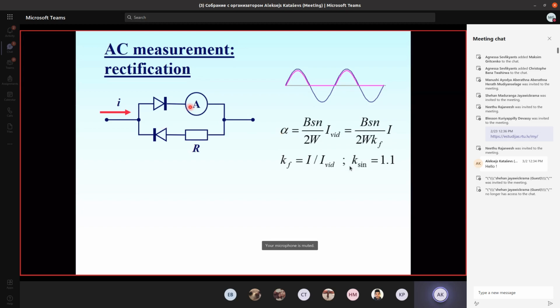We see that the deflection angle is proportional to the average current. It may be recalibrated by altering the sensitivity, adding some shunts, or adding additional resistance, making the angle proportional to the effective current. But the problem is that the ratio between effective current and average current depends on the shape of the signal.